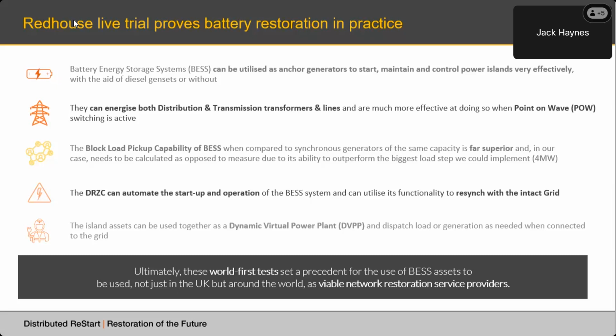The DRZC, which Pete alluded to, the distribution restoration zone controller, we utilized that functionality to automate a lot of the control in the power island that would otherwise be manual, because you can imagine in a genuine black start scenario, and Pete will know better than me, the pressure on the control room is going to be immense. So the more that we can automate, the better, in that it's much better to have a power island that's ready to energize customers as opposed to one that's still building up.